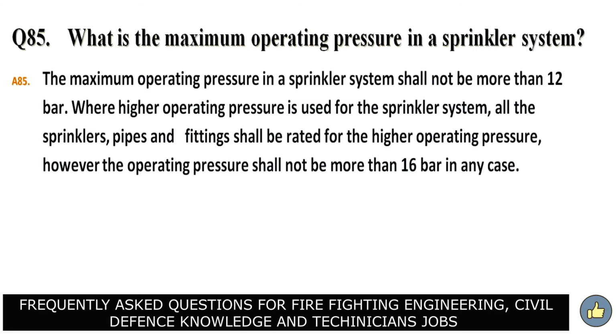What is the maximum operating pressure in a sprinkler system? Answer. The maximum operating pressure in a sprinkler system shall not be more than 12 bar. Where higher operating pressure is used for the sprinkler system, all the sprinklers, pipes and fittings shall be rated for the higher operating pressure. However, the operating pressure shall not be more than 16 bar in any case.